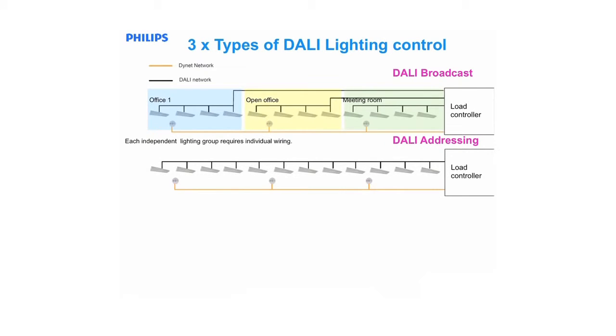The DALI addressing system connects all the ballasts together onto the same network. This allows for only one cable to run to the distribution board. The advantage of this method is that the cabling requirements of a project have been drastically reduced, as 16 different lighting groups can be connected together. This method of installation is much simpler for electrical contractors to apply, requiring less cable and less termination points. This can make the whole lighting control system much cheaper. The motion sensors are connected to a Dynalite cable in the same way as a DALI broadcast.